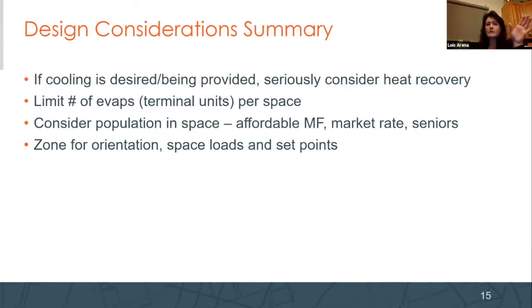So design consideration summary: if cooling is desired or being provided, seriously consider heat recovery. Limit the number of terminal units in each apartment, not necessarily per space, but in each apartment. Consider population in the space. Is it affordable multifamily where you're going to have really high density and a lot of internal gains? Is it market rate where you're going to have less internal gains? Are you going to have seniors that really want a warm apartment, right? Like all of these things come into play. And then zone for orientation, space loads, and set points. Make sure that all three of those things come into play when you're doing this.